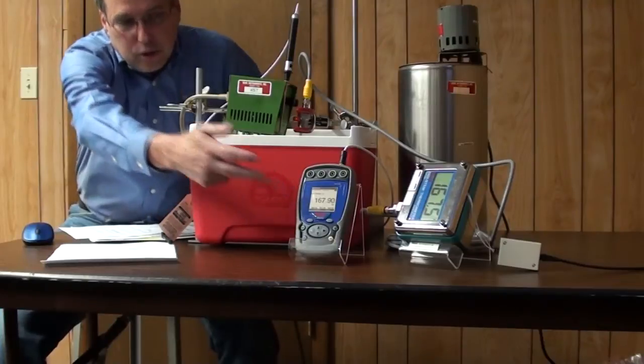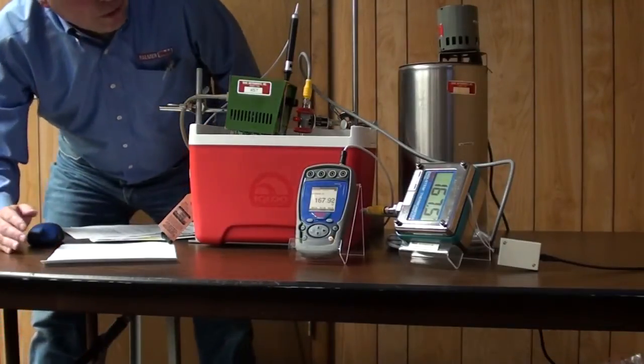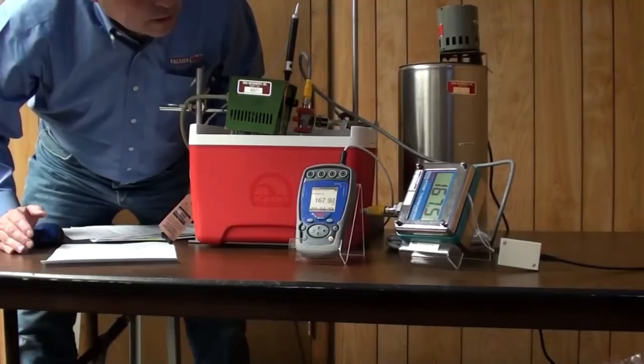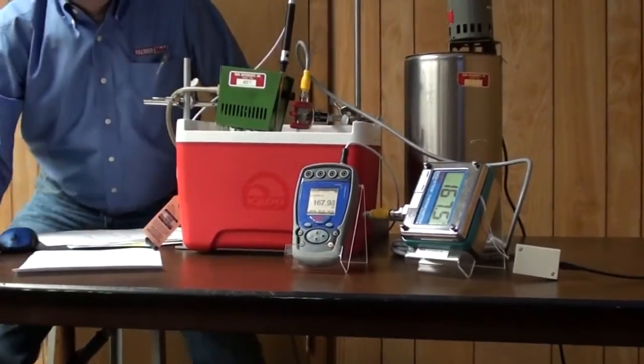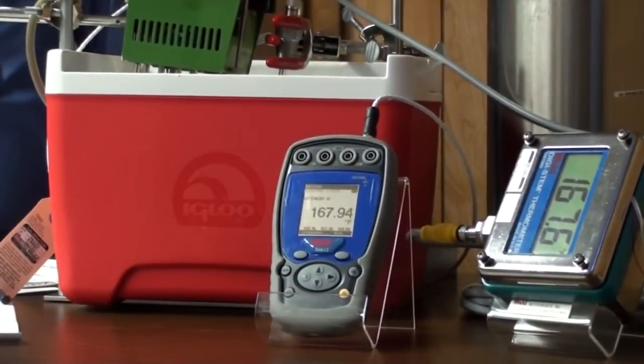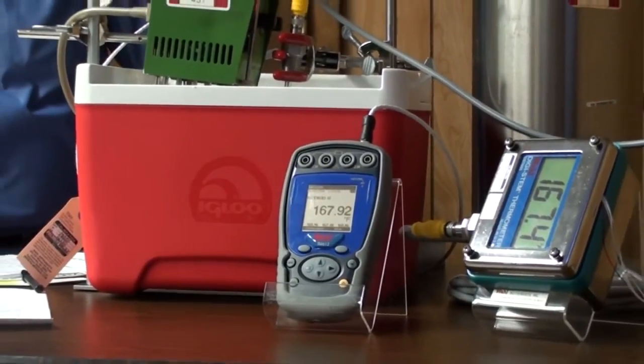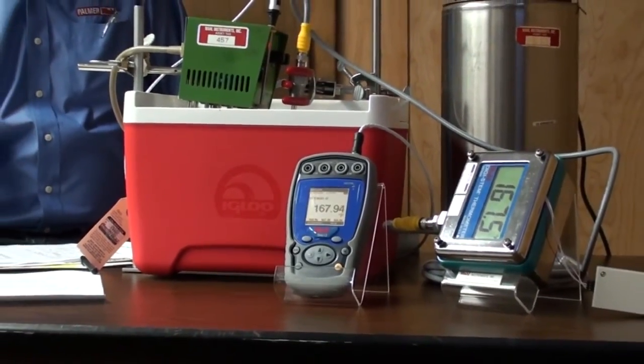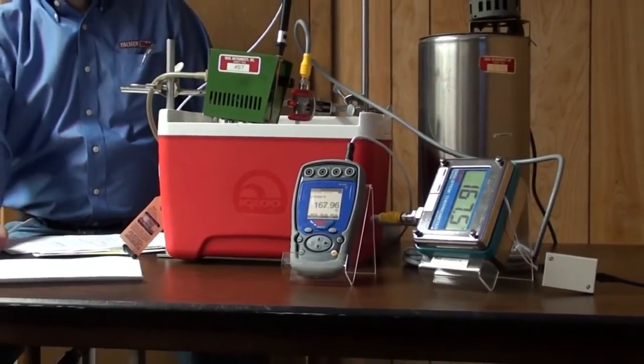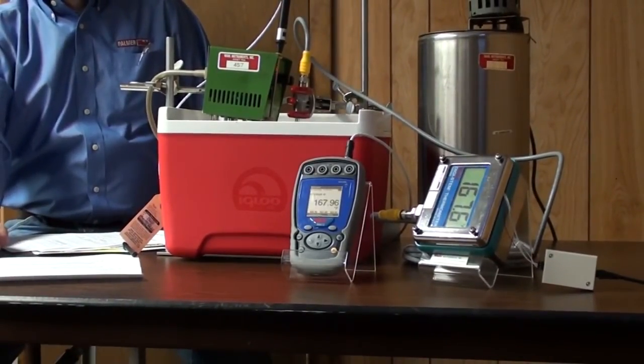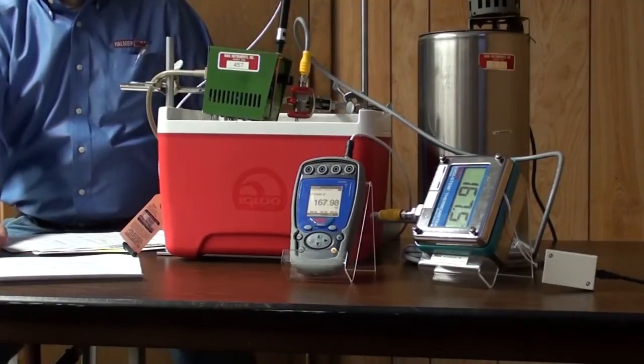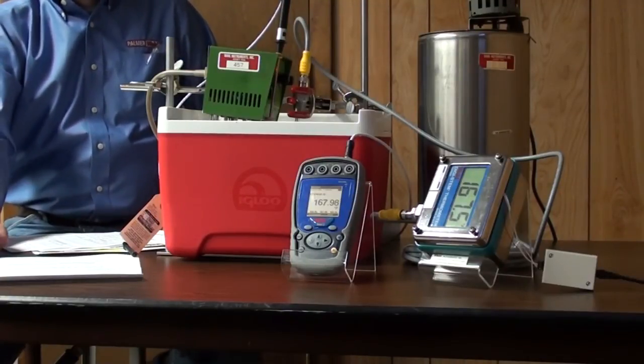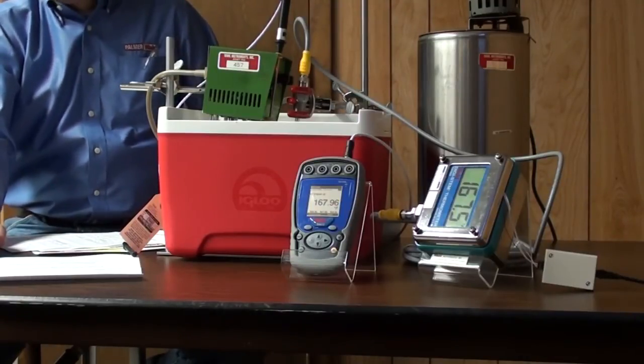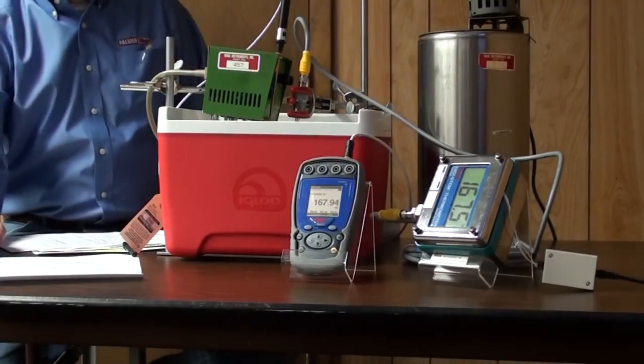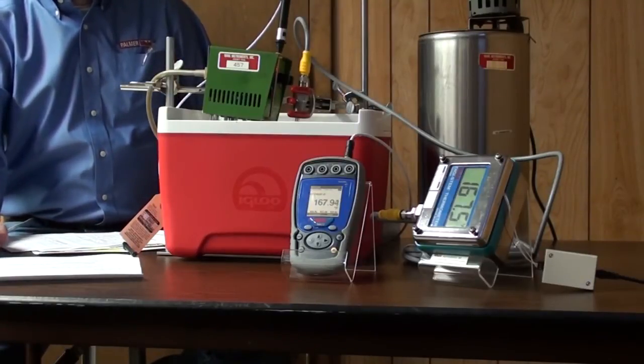When we get to our unit, whatever the temperature is on the unit there, I can't read that one, 167.9, that's going to be what we record in our indicated space. And then the unit under test is where the display reading goes. Deviation is the difference between these two. This would be from our procedure, so if it's before data, it would be 0.3. If it was after, it'd be 0.2. Then we check if it's in or out of tolerance, however you choose to convey that information.